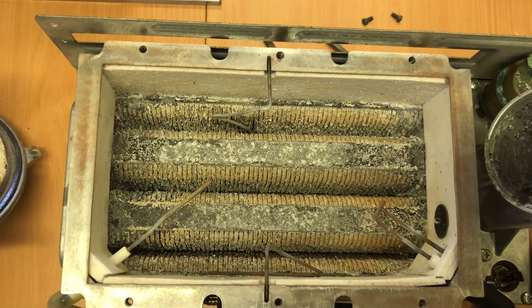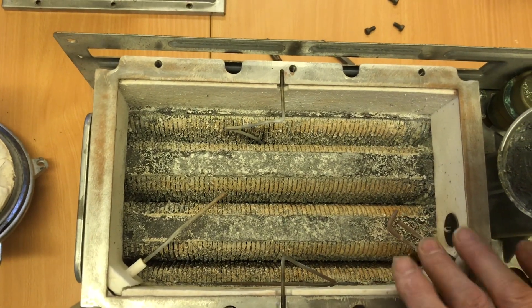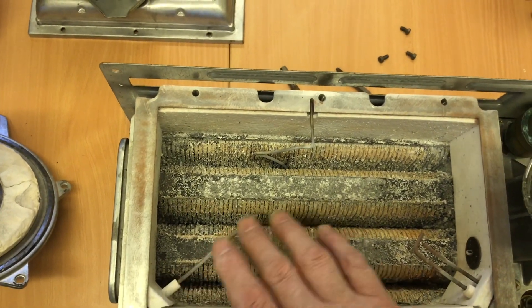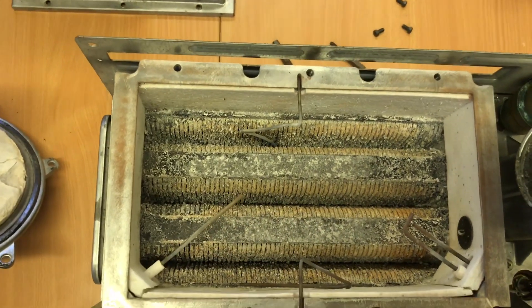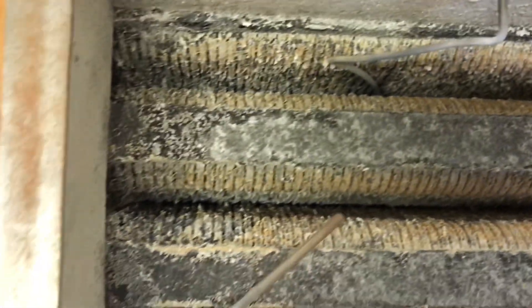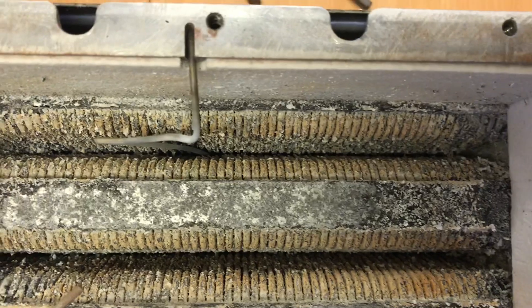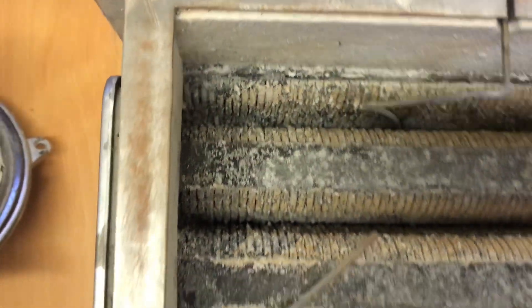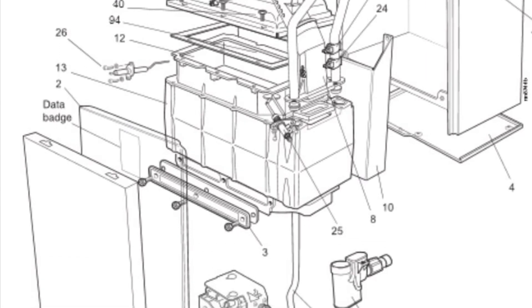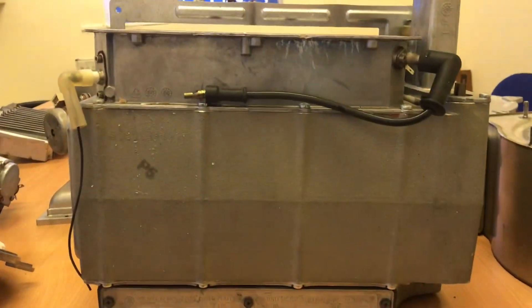You can see the spark igniter here — this is where it lights the gas — and the flame rectification/flame conduction system tells the PCB that the gas has burnt across. You can see this heat exchanger is in quite poor condition; it's been taken out because it corroded and was leaking. It's not a very robust heat exchanger at all. In 1992, Heat Systems joined the Bosch Group to become Worcester Bosch Boilers.